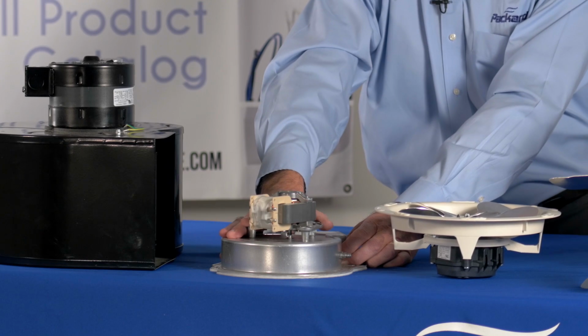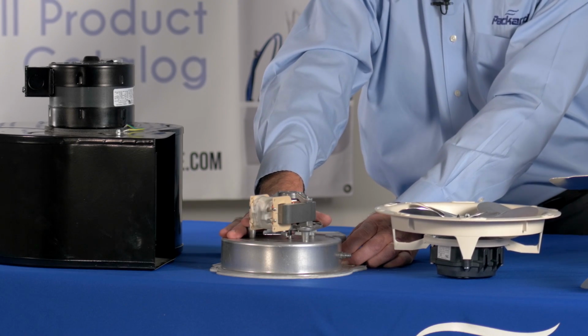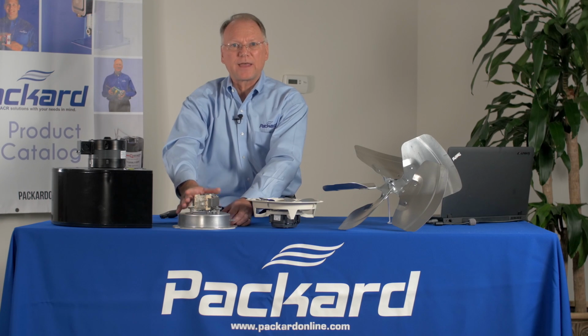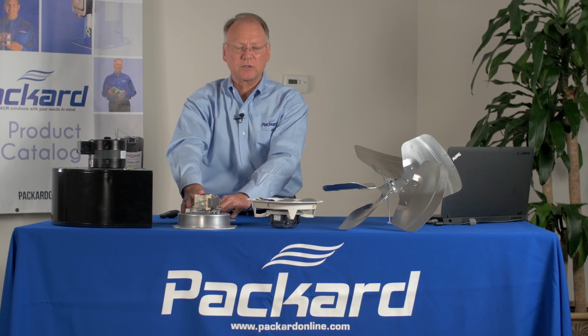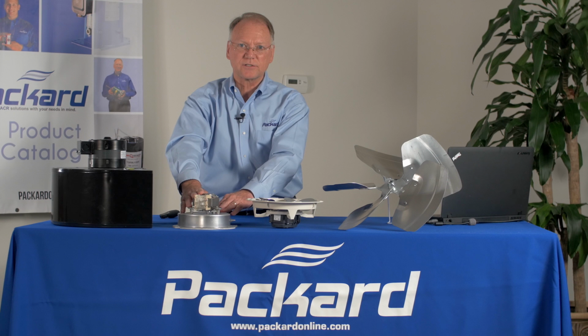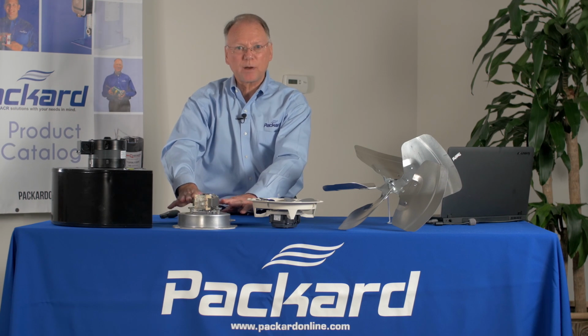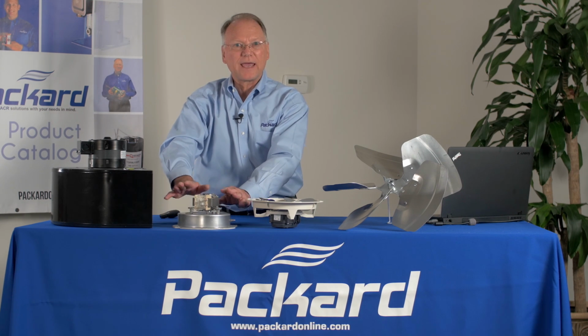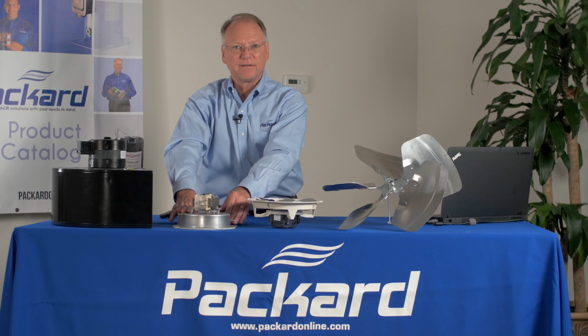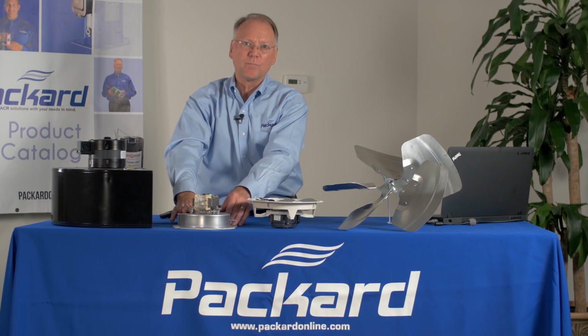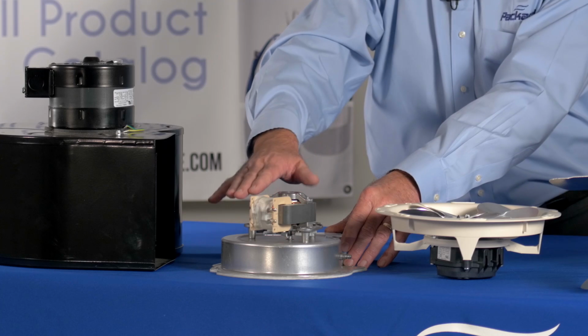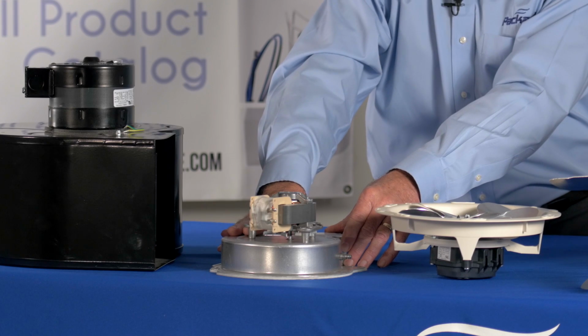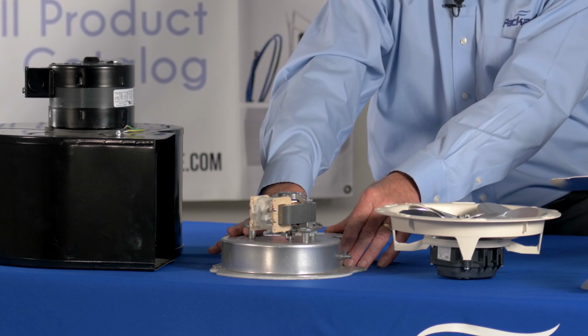Those consist of primarily carbon monoxide. So the draft inducers are designed very specifically for individual furnaces and need to be replaced with a duplicate design in order to have proper combustion and proper removal of carbon monoxide so that there are no hazardous situations that occur in the living area.